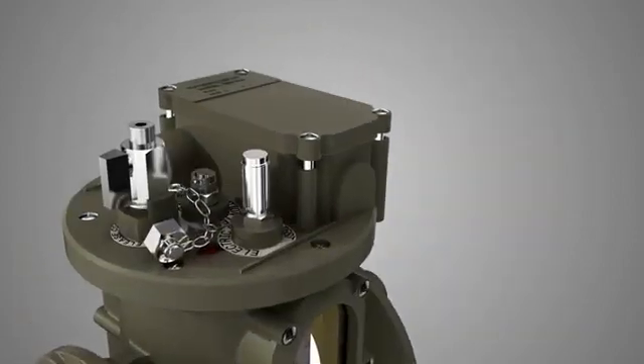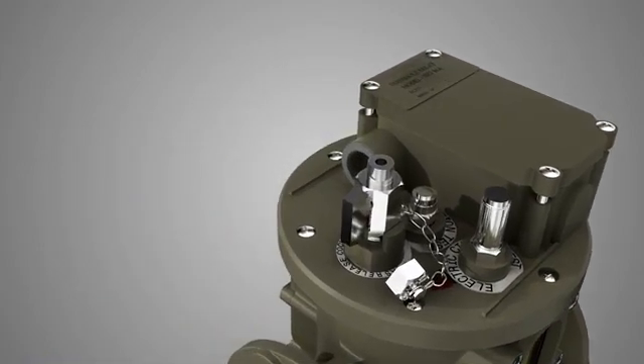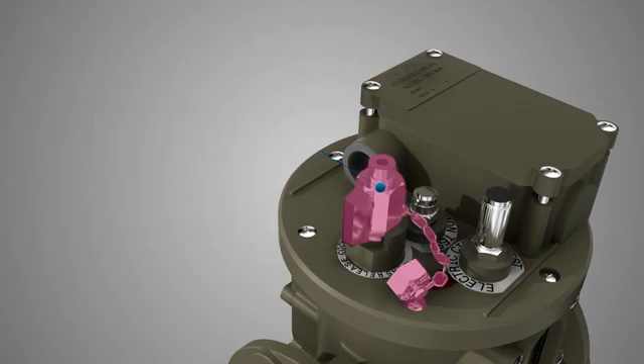Electric circuit test device with cap for manual checking of switches is provided on the cover of BR. A gas release cock with cap and chain is provided on the BR cover to collect the gas generated inside the BR.